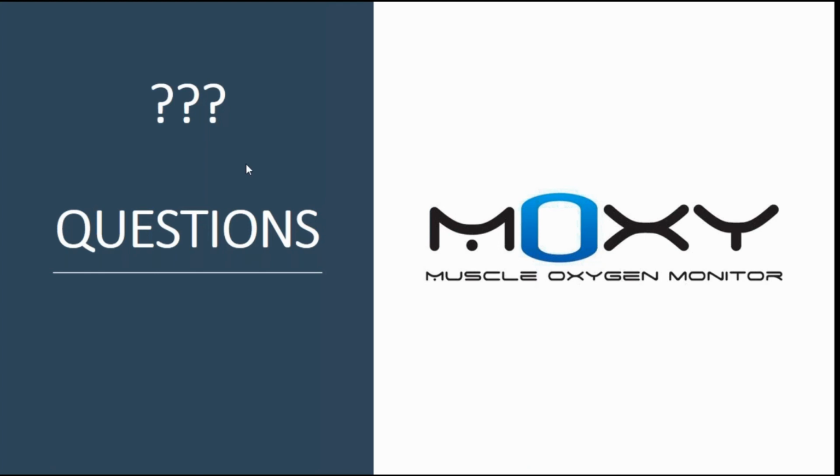One question here. What about location on the body? That's very important, and that's one of the things that the Moxy algorithm allows us to be flexible with. Because we can handle a wide range of fat layer thickness, we can go over a wide range of body positions. But the Moxy is based on a layer of skin, fat, and muscle. So measuring on a skull, I don't know what's going to happen. It's not designed for that. So we want to be on a muscle location. The fat layer thickness does need to be less than about 12.5 millimeters. Otherwise, we just don't get enough light from the muscle to take a valid reading. So we can measure anywhere within those conditions.